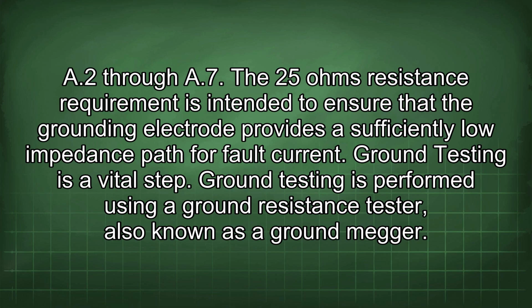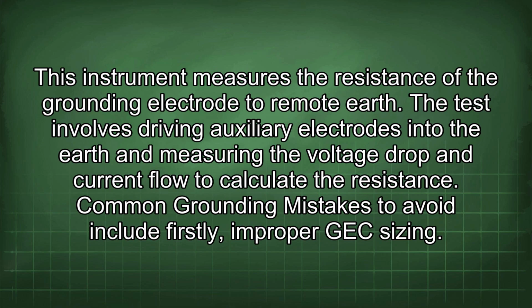Ground testing is a vital step. Ground testing is performed using a ground resistance tester, also known as a ground megger. This instrument measures the resistance of the grounding electrode to remote earth. The test involves driving auxiliary electrodes into the earth and measuring the voltage drop and current flow to calculate the resistance. Common grounding mistakes to avoid include: firstly, improper GEC sizing.